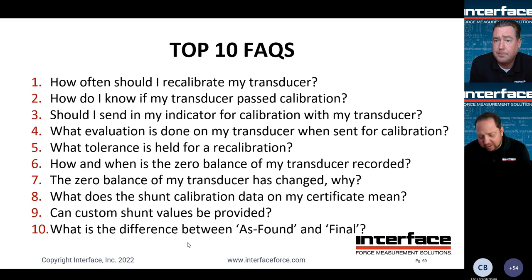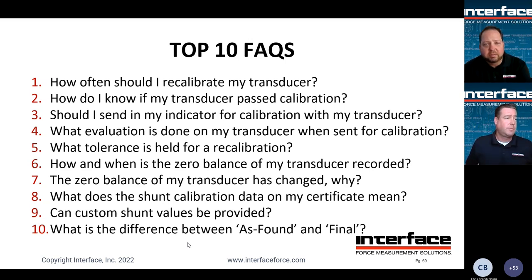Yeah, but if it's a sensor you've got a lot of confidence in, you can extend that interval. We have some reference standards that are on 2 or even 3 year, maybe even 4 year for some of the older ones, cal intervals, because of our extensive confidence around it. But yeah, first year is a good rule of thumb. It's not a bad rule of thumb to follow. Zero balance checks, of course, are a good way to see if anything seems to be changing with regards to the health of the transducer.